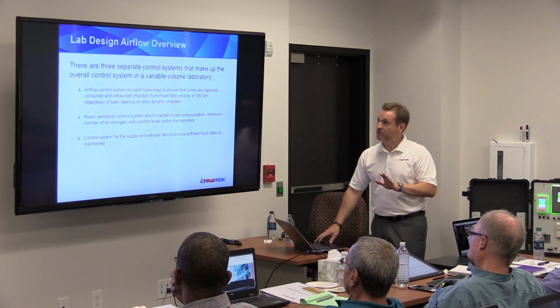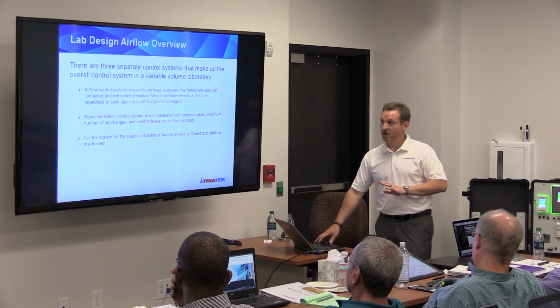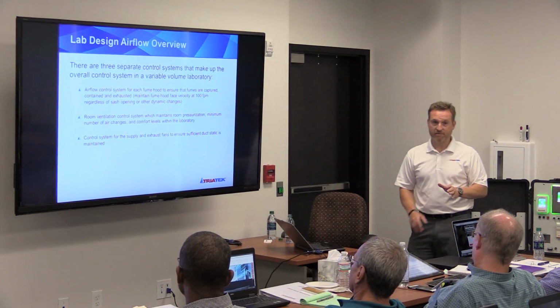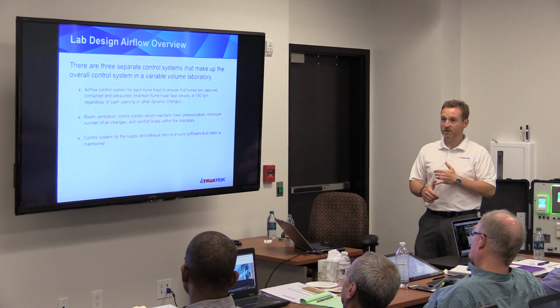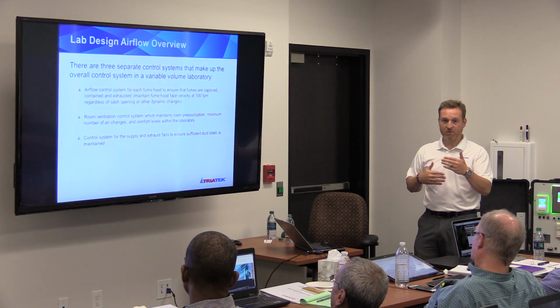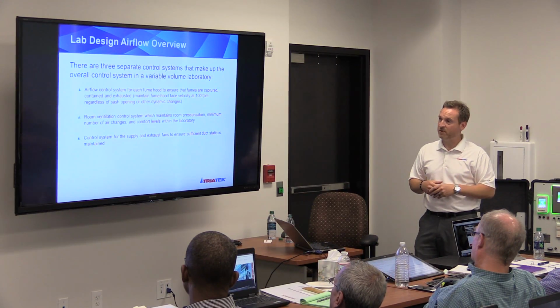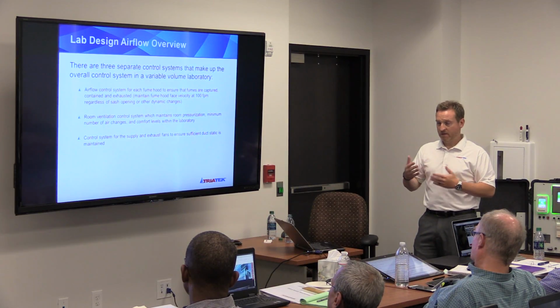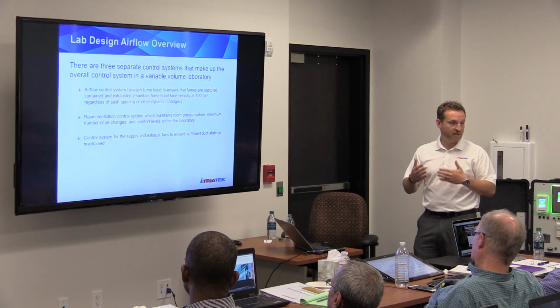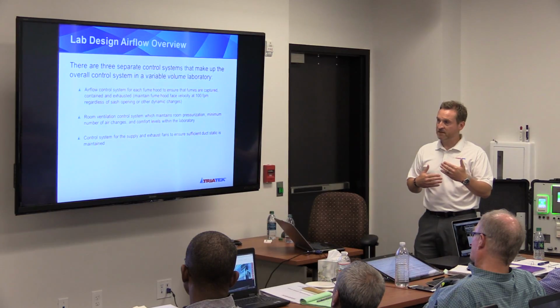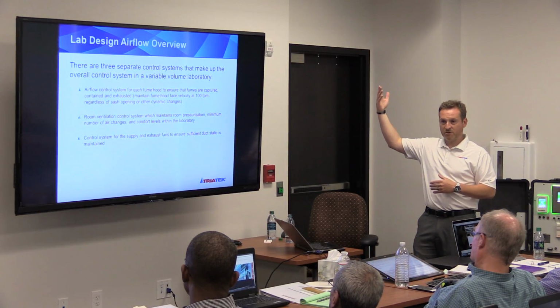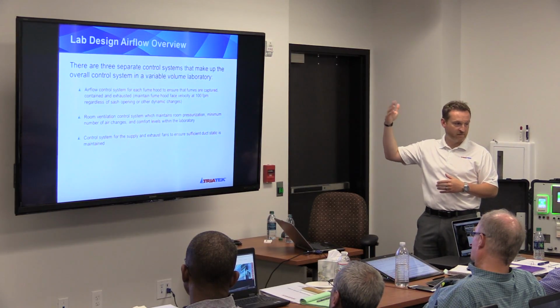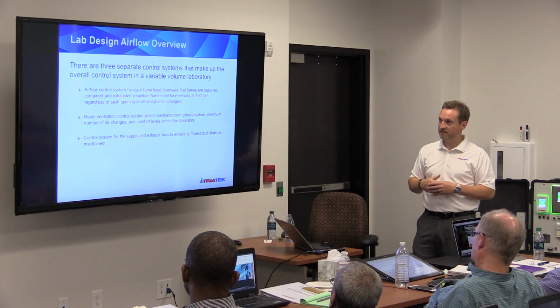In a laboratory, there's three separate systems that make up the overall variable volume lab. All right. First and foremost, the fume hood controller. We've got to make sure that we're maintaining proper face velocity of the fume hood. And then also a room ventilation system. The room ventilation system has to maintain the offset of pressure for the space. And then also the control systems for your supply and makeup air and exhaust fan systems.